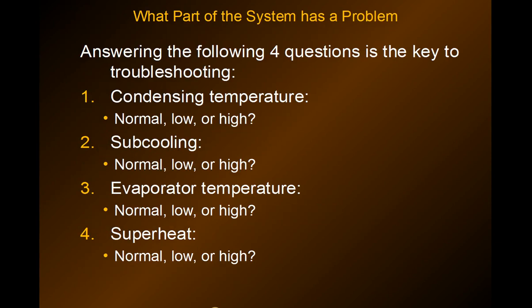Then you answer the following four questions, which are the key to successful troubleshooting: Is the condensing temperature normal, low, or high? Same with the subcooling, same with the evaporator temperature, and same with superheat as well.